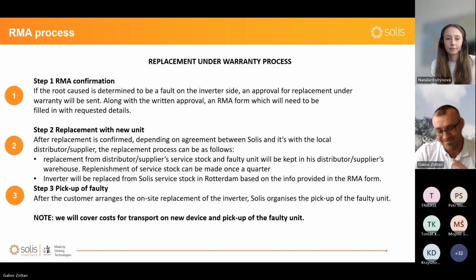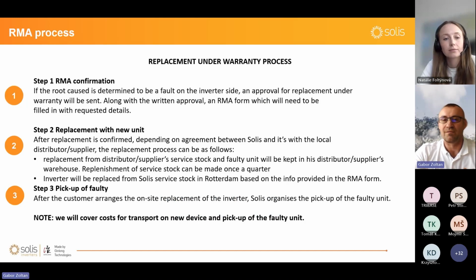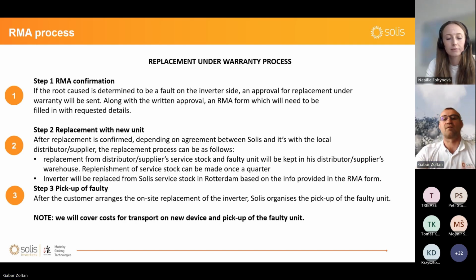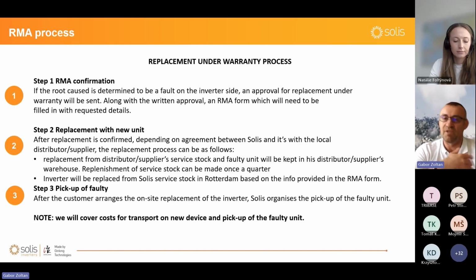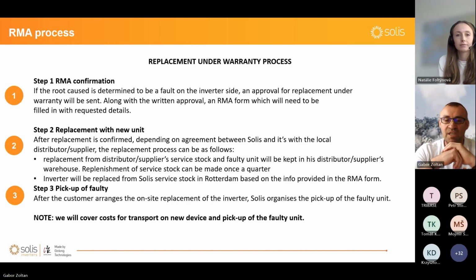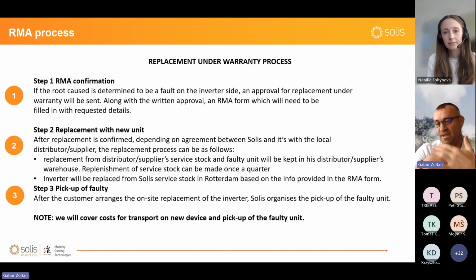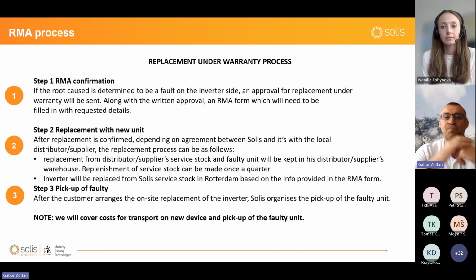When we realize we cannot repair the inverter, we will start the replacement. But for the replacement, you cannot just send that it's not working and we will change it. No, we need measurements. We need to confirm that with investigation.